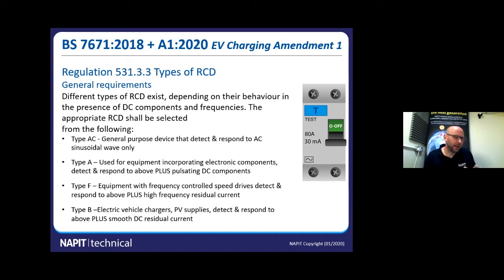Okay, excellent. So basically what we're saying then, if the DC leakage from the batteries, car, whatever, starts to cross into the circuit, the type A RCD will work fine up to 6 milliamps. If it goes above 6 milliamps, we know from the product standards that the type A RCD is no longer any good. So now we're relying on the DC monitoring in your unit to shut the circuit down. Is that how I understand it correctly?